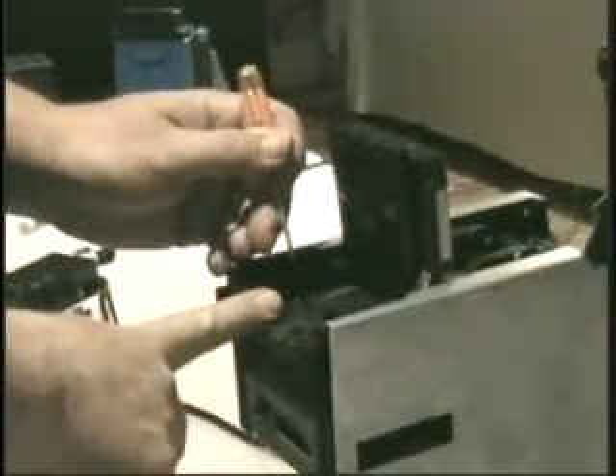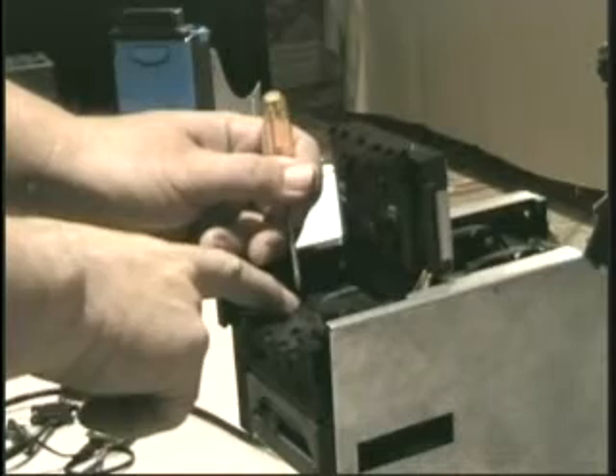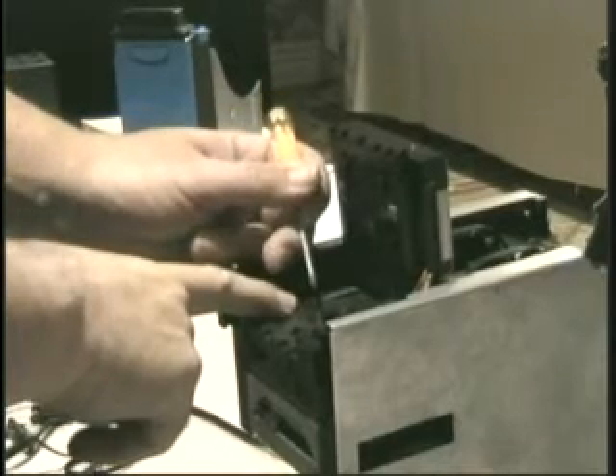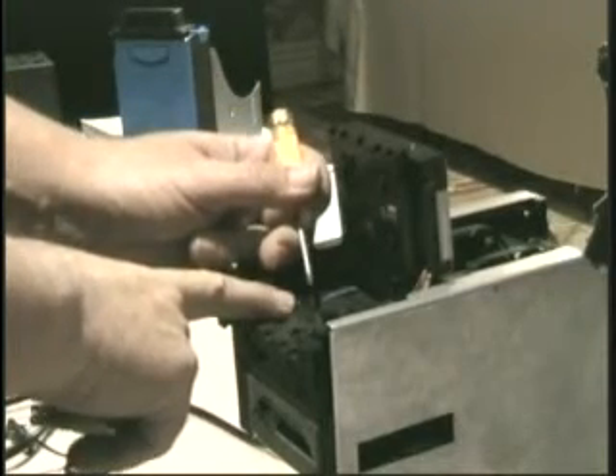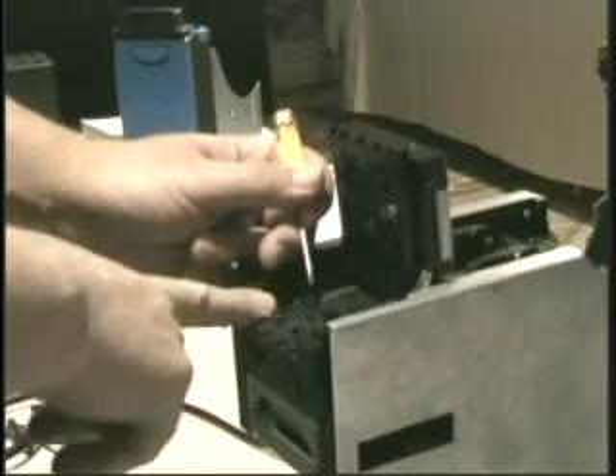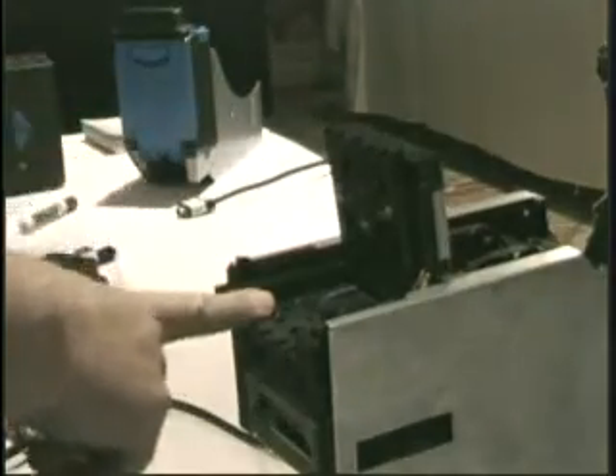You don't want to use anything metal on those rollers in the head, for a couple reasons. First, it's right next to the lens, if you slip you'll scratch it and then have to replace the lens, and pulling this apart to replace the lens is a lot harder than just cleaning the rollers. You want to use something as soft as plastic or softer.